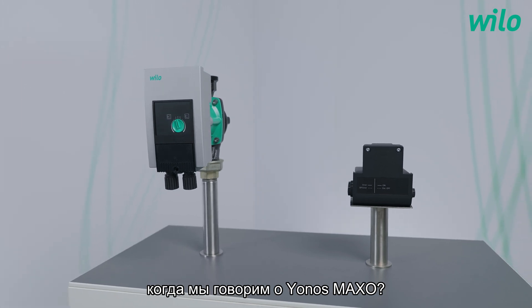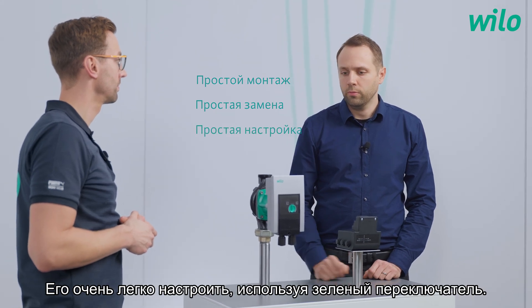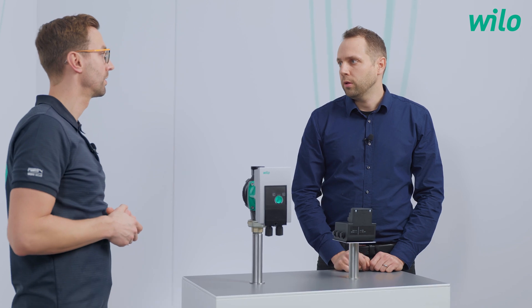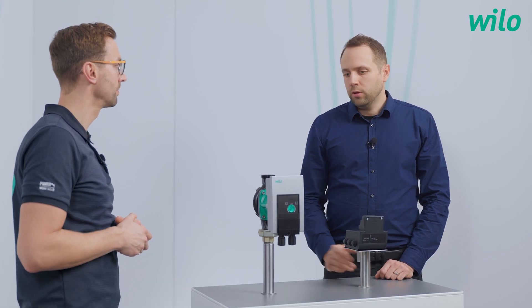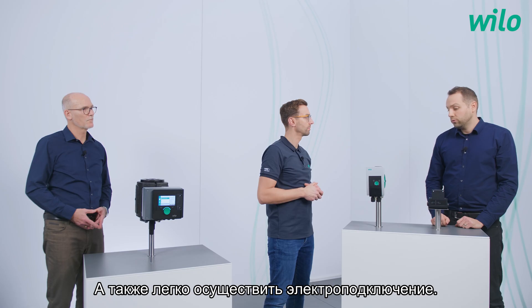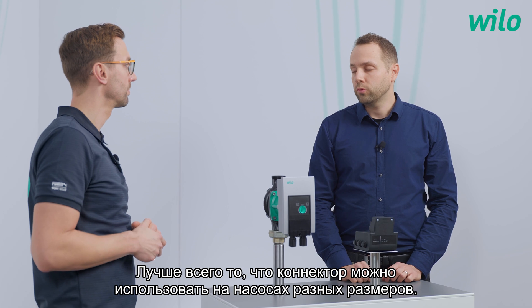André, what are the main advantages of the Yonos Maxo? First, there's easy installation. Second, it is easy to reuse in case of a replacement to exchange an existing pump. It is also very easy to set up using the green knob on the front. It has a simple display where you can set the control modes via this knob, and the display shows basic information like the adjusted head or error codes. Easy replacement — what does it mean? It has a very compact design, so the Yonos Maxo fits perfectly when replacing a small pump. Additionally, the electrical wiring is easy: you can remove the plug, do the wiring, and plug it back in. Best of all, this plug can be used across all pump sizes, making it easy for the installer during installation and setup.